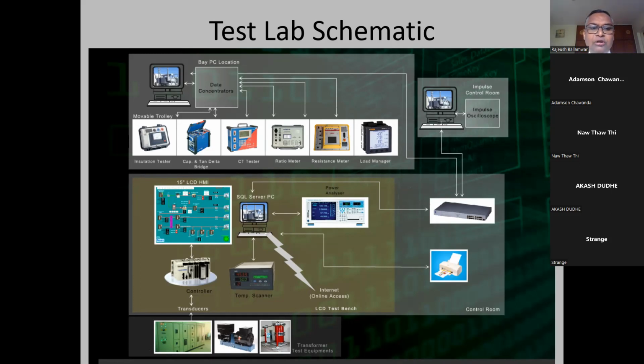You can also see the controller, which is interfaced with the MCBs, the ACBs, the air circuits, all kinds of breakers. It could be a motor generator set, a variac, a static frequency converter, or an HV tester - all kinds of equipment that play a role in testing transformers will be interfaced to the controller. You also have the temperature measurement device.